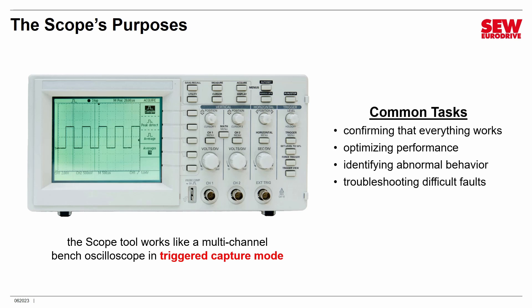Common things we do with the Scope built into Movitools Motion Studio include confirming that everything is working. We monitor various parameters and look at them on the Scope to confirm everything is okay. We can use it for optimizing performance, examining parameters to make sure the response is what we want. The Scope is also used to identify abnormal behavior — monitoring certain parameters can reveal adjustments that need to be made. Finally, the Scope is often used for troubleshooting difficult faults, and we'll look at how to do that before we're finished with this session.